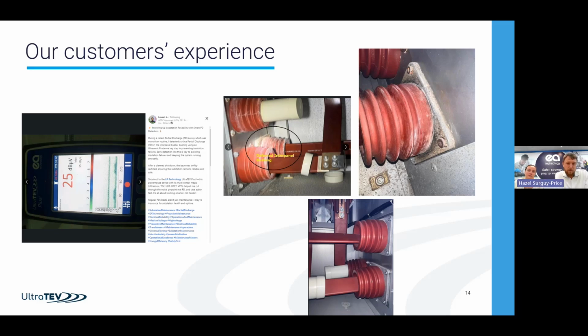And the slow breakdown of those bushings. The nice bit here is if you find this early enough, the replacement is easy. The service and cleaning up the surfaces, putting it back to addressing your clearances and put it back into service can be done relatively quickly. So there's a real benefit to the customer of doing these surveys, identifying kit early before that leads to failure. As we've seen from the previous slides, it would eventually fail.